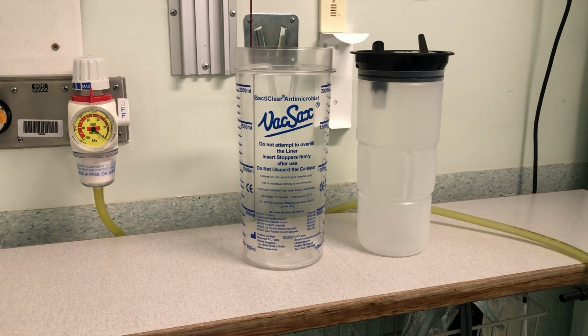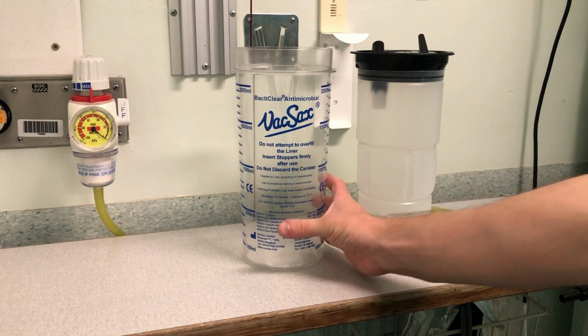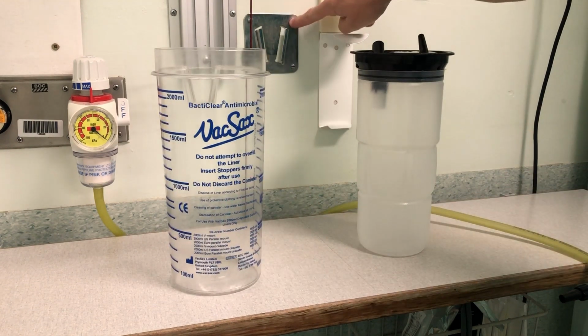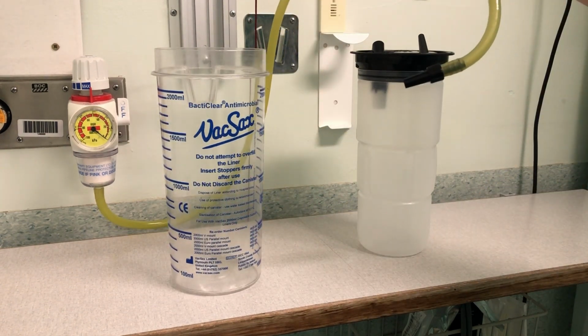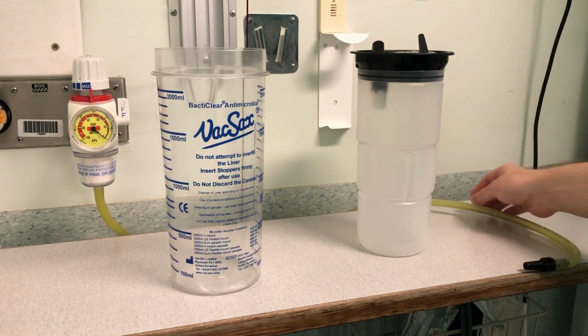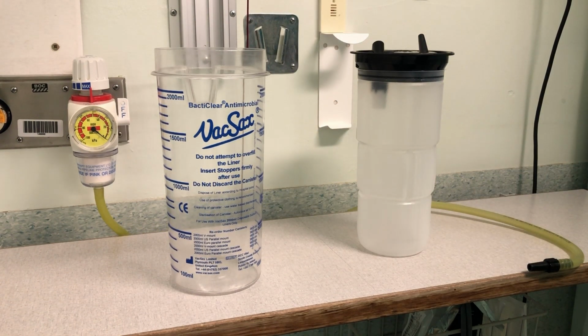How to be sure relevant parts and accessories are available. The non-disposable parts are the canister holder, and the yellow tubing, taper and T-piece if it is in use. It's dependent upon canister size and or area. Please note that the tubing kits do not require changing between patients, as they are protected from internal contamination by the filter within the suction liner. Any external contamination may be removed with disinfectants. Should the tubing kit become obviously internally contaminated, it should be replaced. The tubing kits have a 7-year life and should only need replacing if damaged or internally contaminated.